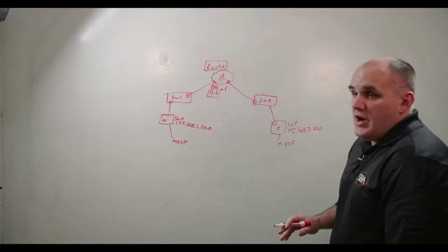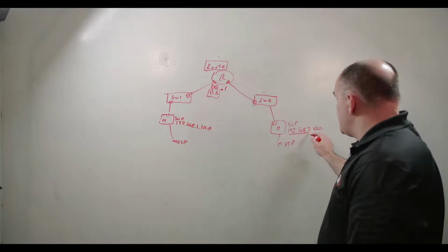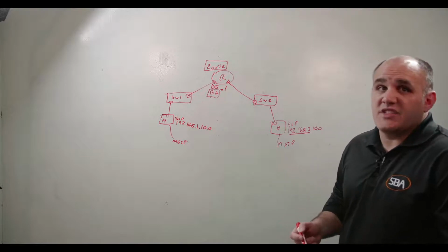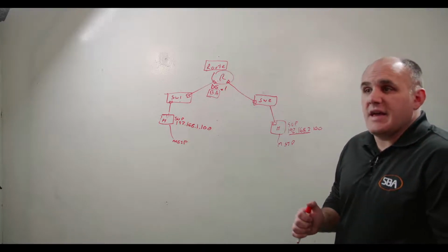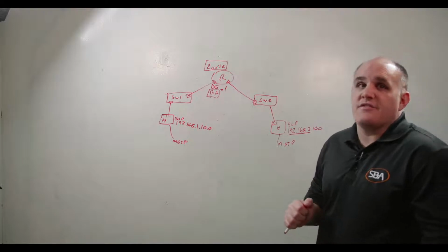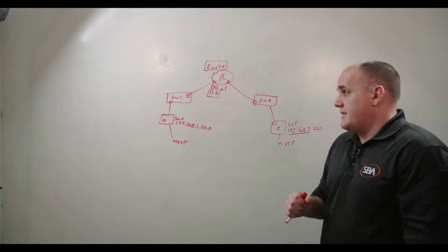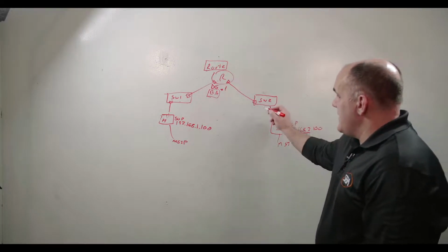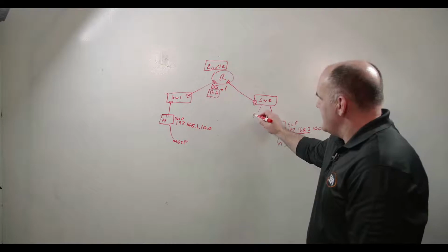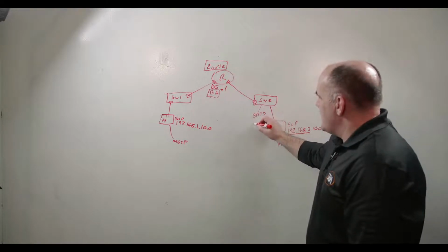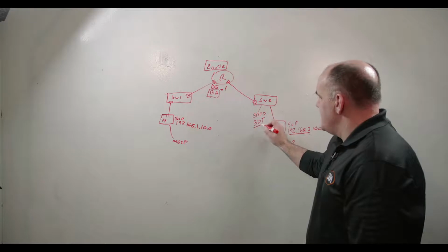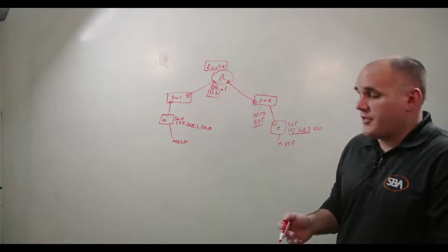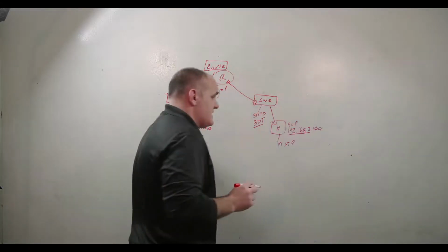Then what we need to know is what subnets these are, because we would go and create our BBMDs. Now, I'm not going to dive into BBMDs because we've discussed BACnet in detail in previous episodes, and we're going to be discussing it in further detail in upcoming episodes. But what I want you to understand is that by knowing the subnet, then at the BBMD, that's hard to say fast, you can enter into your BDT entries the different subnets that need to have communication traffic flow through them. So if we didn't understand this, then we wouldn't know.